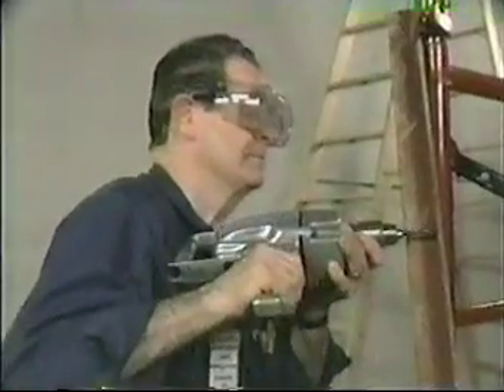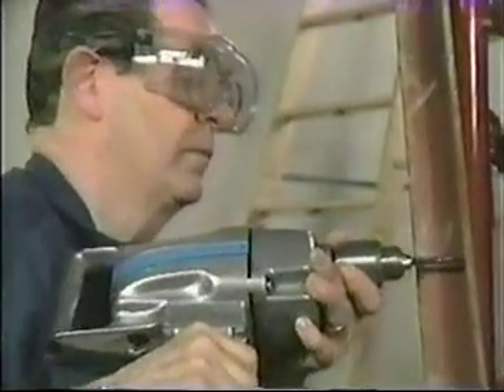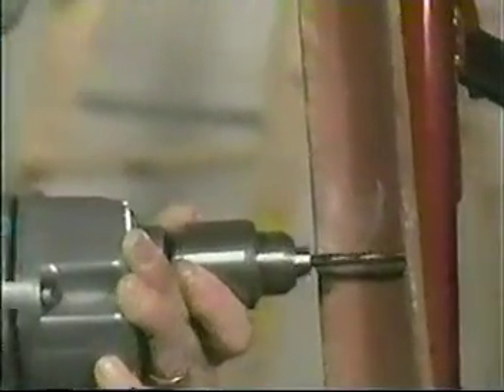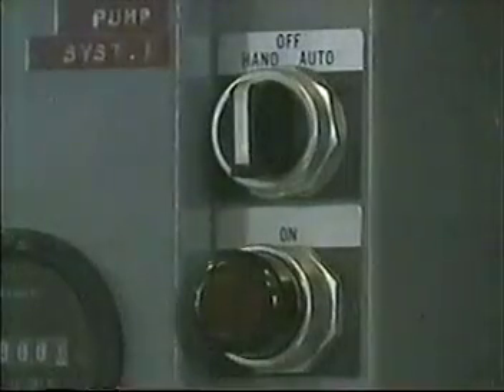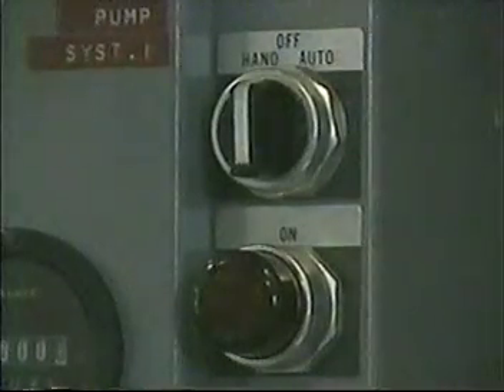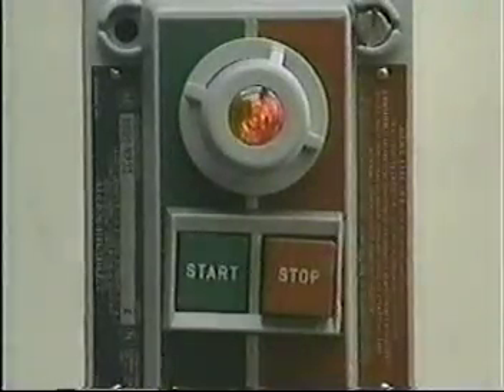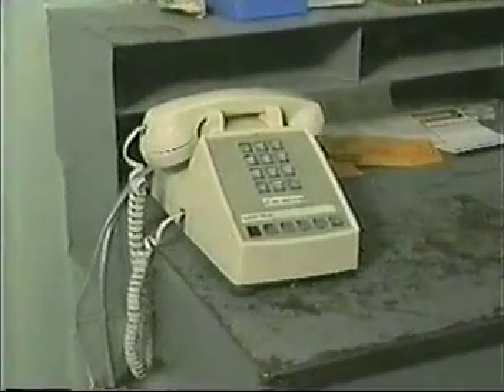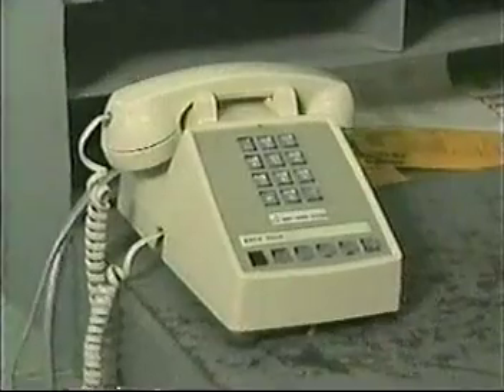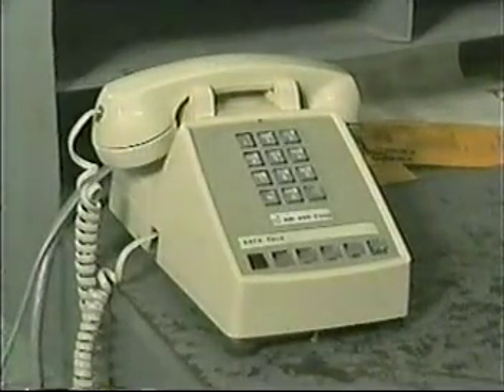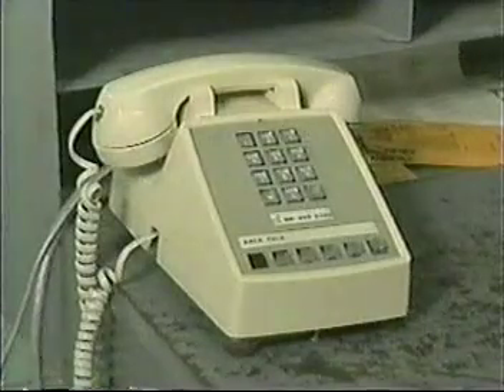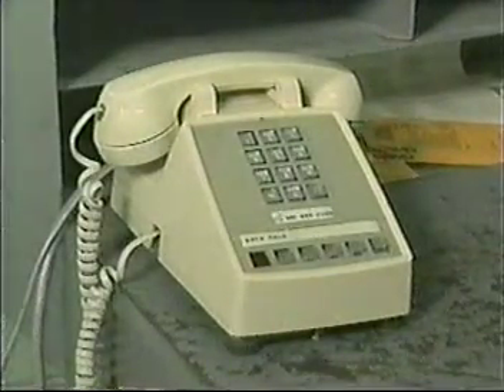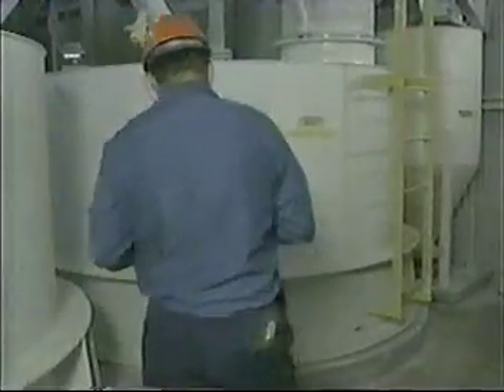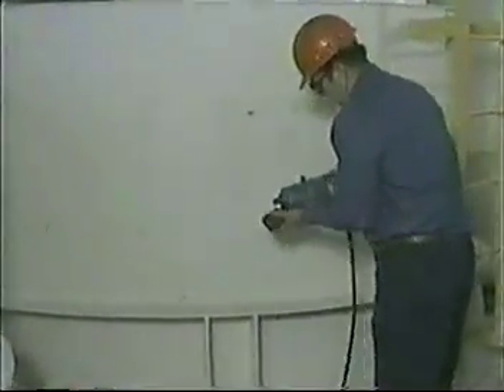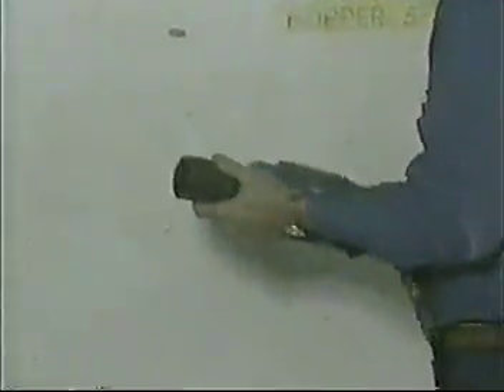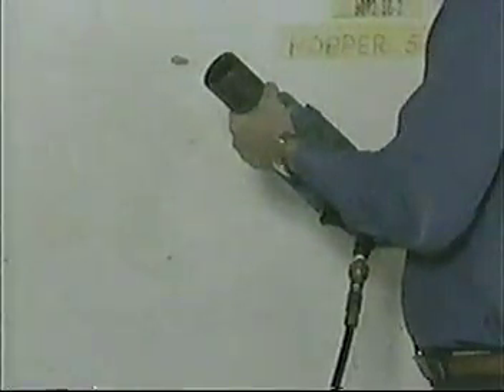Many electric motors, including those used to drive battery-powered screwdrivers and drills, produce continuous internal arcing during normal operation. Relays, switches, actuators, distributors, and other devices produce sparks each time they function. Even tiny electrical sparks from sources such as the switching of a battery-powered flashlight or the bell of a telephone can be enough to trigger an explosion and fire if flammable vapors are present in the proper mixture. For this reason, pneumatic or hydraulic-powered equipment or non-sparking hand tools should be used whenever there is any possibility that flammable vapors may be present.